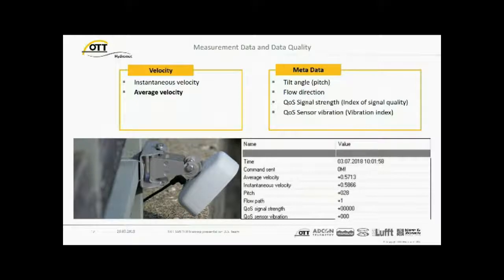Measurement data. What can we expect to get from the instrument? Of course, the most important is velocity. So we will get instantaneous velocities, and we get average velocity. If you want to compute discharge and you don't want this big up and down on the water surface, or the turbulence, and you want a good average value, then you will take the average velocity of the output stream.